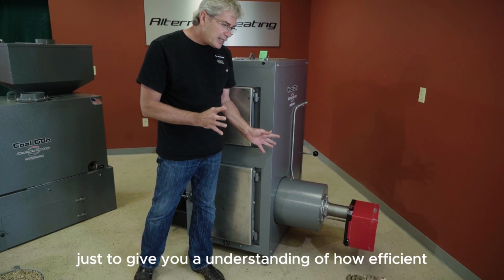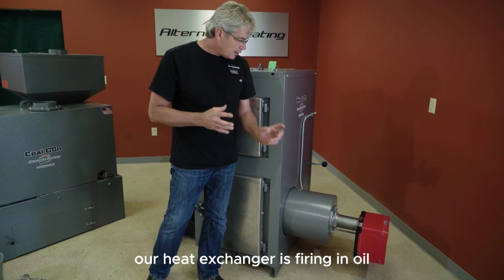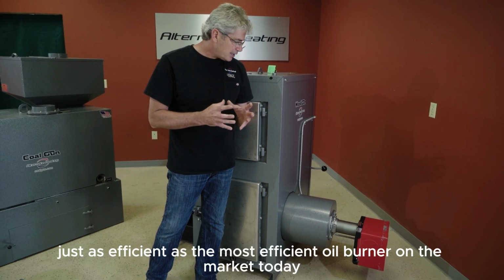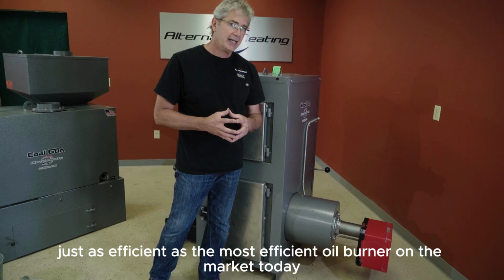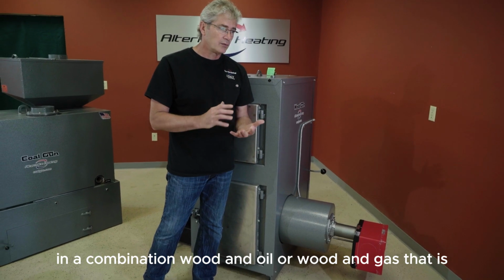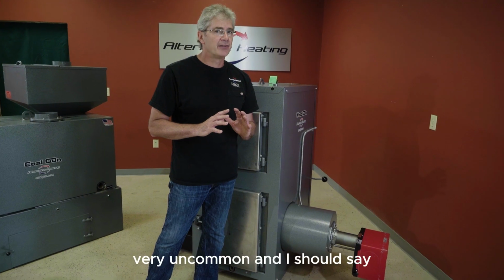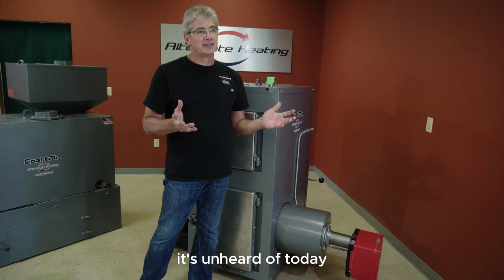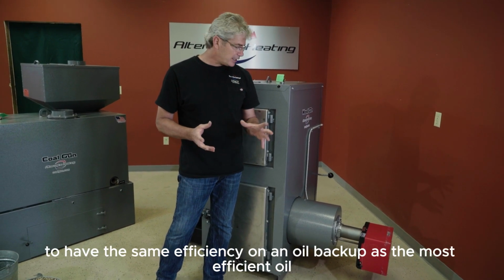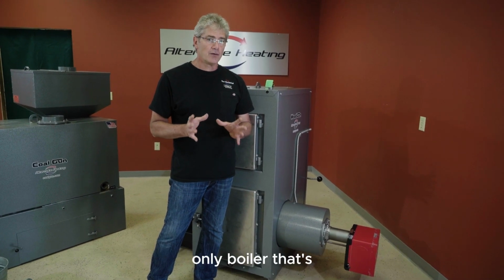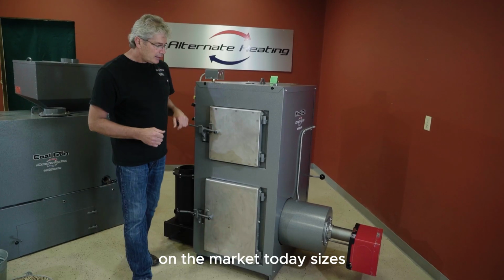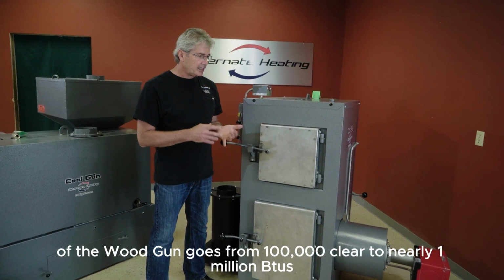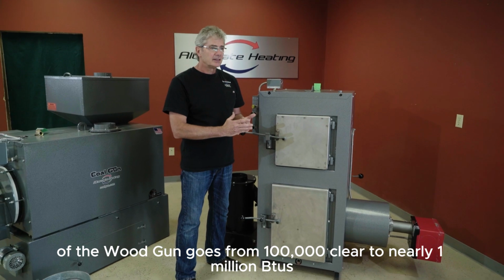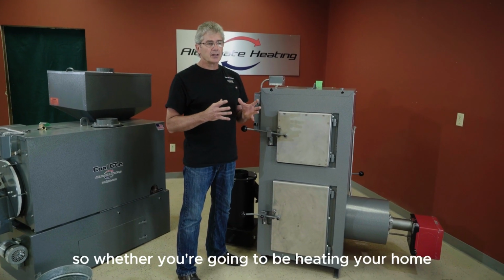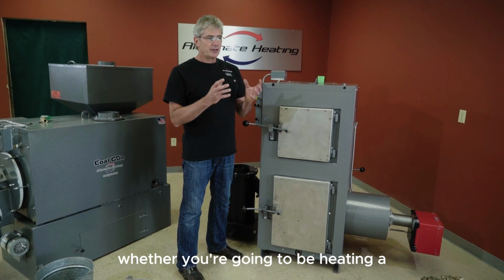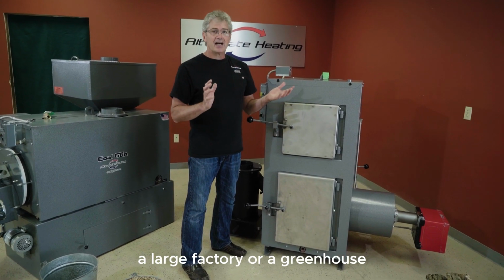So just to give you an understanding of how efficient our heat exchanger is, firing in oil, we can be just as efficient as the most efficient oil burner on the market today. In a combination wood and oil or wood and gas, that is very uncommon. And I should say it's unheard of today to have the same efficiency on an oil backup as the most efficient oil only boiler that's on the market today. Sizes of the wood gun go from 100,000 clear to nearly 1 million BTUs. So whether you're going to be heating your home, whether you're going to be heating a large factory or a greenhouse, we have you covered.